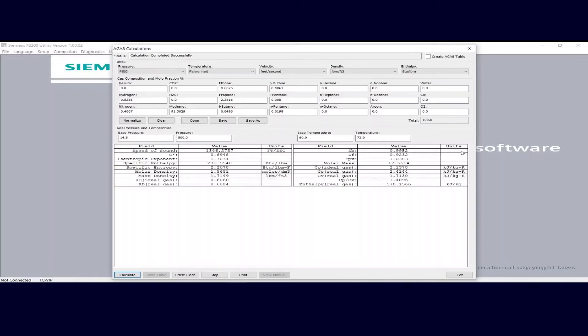Knowing the compressibility value will enable you to enter it into the flow meter so that you can do standard volume correction right at the meter without the need for a flow computer. This is also important in the case where you might want to do local standard volume correction for comparison to an in-situ meter. If we change pressure — say our pressure is now 800 — our speed of sound will change along with our actual compressibility factor ZF. This is a valuable tool for getting these calculations and your overall gas enthalpy calculations.